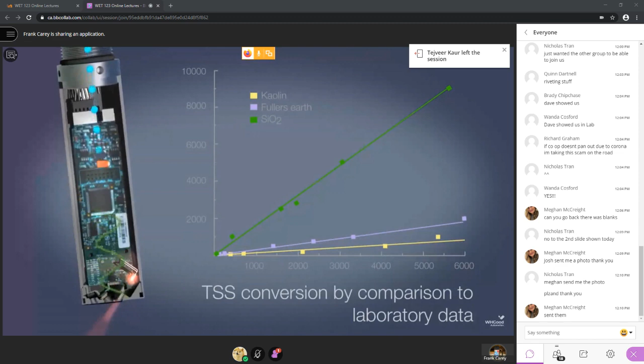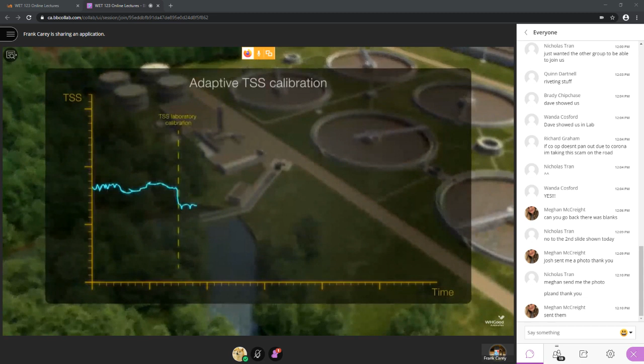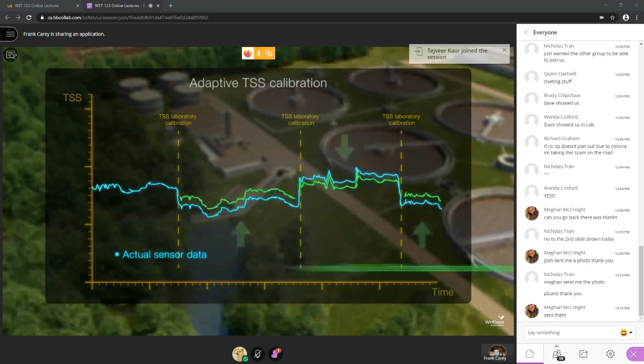The scattered light detected by the sensor is directly proportional to the turbidity of the sample. Analysis of the signal conditioning is conducted within the robust sensor housing and transmitted digitally to the transmitter. The turbidity measurement can be used to determine the total suspended solids, or TSS, of the sample by comparison to laboratory data. The ATS-430's adaptive TSS calibration feature enables the sensor to intelligently calculate the TSS conversion based on historical process data.